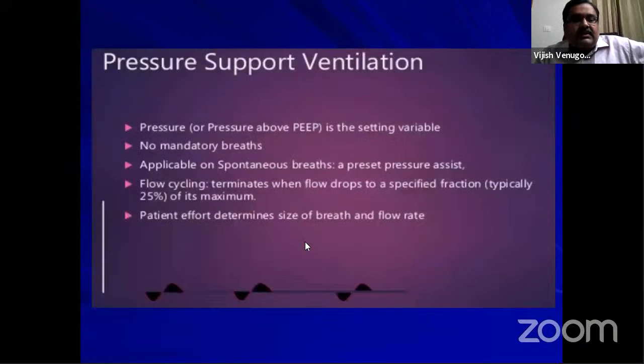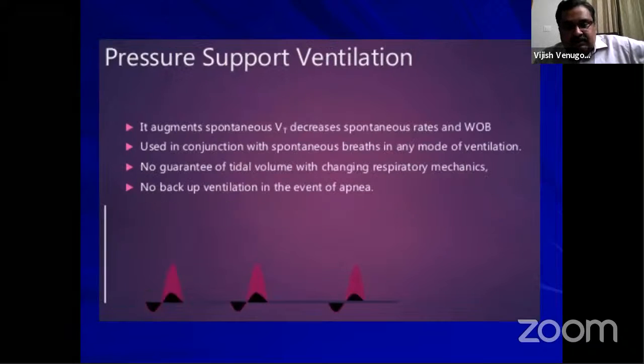So what is pressure support ventilation? Here you can see that this is the picture below. It is showing spontaneous ventilation. That is a sinusoidal pattern. Here pressure above PEEP is the setting variable. There are no mandatory breaths applicable on spontaneous breaths, and the flow cycling is there, which we have gone through, which terminates when the flow drops to a specified fraction of its maximum. And patient effort determines the size of the breath.